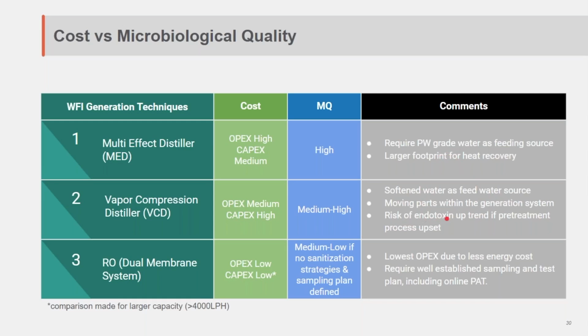As you know, the risk of endotoxin will be on an uptrend if the pre-treatment process is upset, right? The third, the dual membrane system, is relatively low OPEX and low CAPEX, and I'd like to let Ranj continue with the comparison of the dual membrane system. Ranj? Yeah, when we talk about dual membrane systems, we're talking about RO, EDI, UF. So you have the RO and the UF as a double membrane barrier, and the UF is there to reduce the endotoxins to meet the requirement spec.